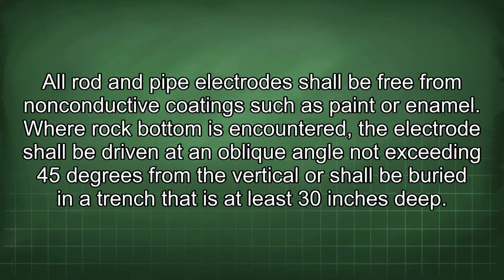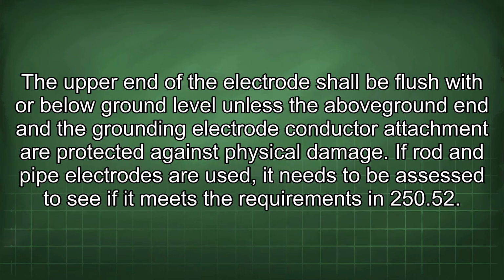All rod and pipe electrodes shall be free from non-conductive coatings such as paint or enamel. Where rock bottom is encountered, the electrode shall be driven at an oblique angle not exceeding 45 degrees from the vertical or shall be buried in a trench that is at least 30 inches deep. The upper end of the electrode shall be flush with or below ground level unless the above ground end and the grounding electrode conductor attachment are protected against physical damage.